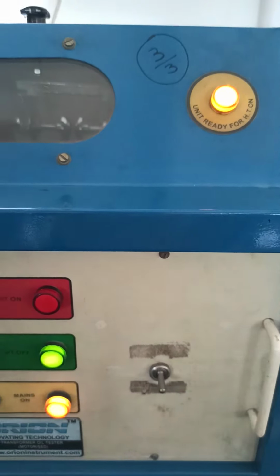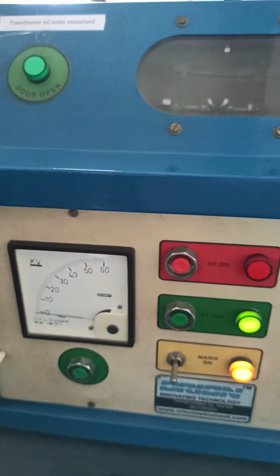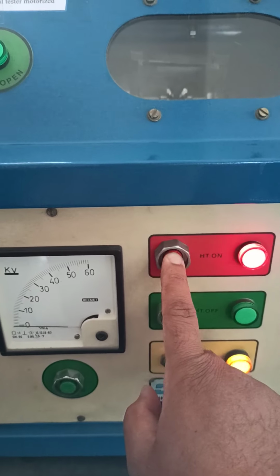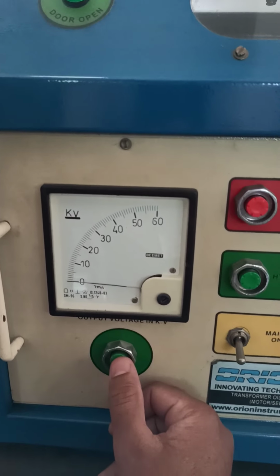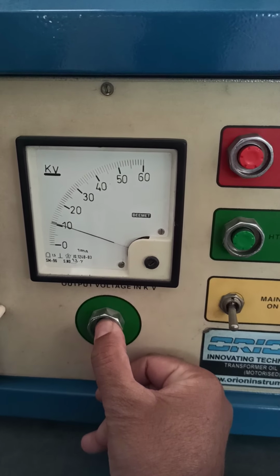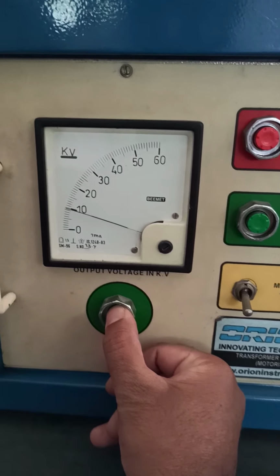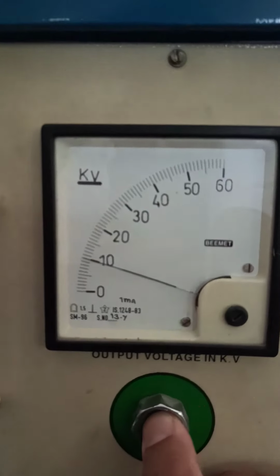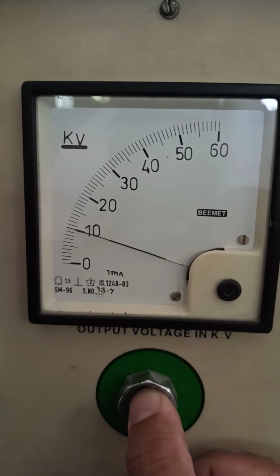Again I will put it in the lower position, and then I will start the test. So you can see inside that you will observe the arc. Okay, I hope you have observed the arc. Now I have to see the value, at what point this arc is produced. So I will press this, and you can see it is giving you the value 10 kilovolt. Okay, 10 kilovolt. It is exactly at 10 kilovolt.